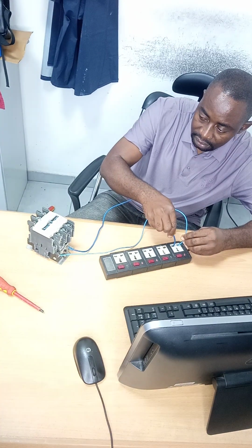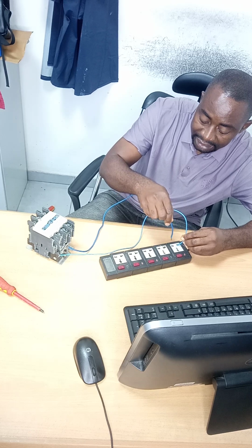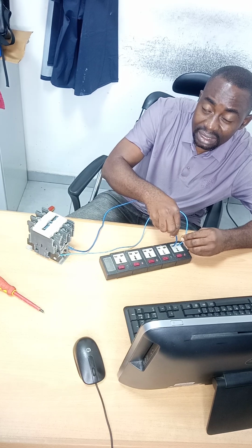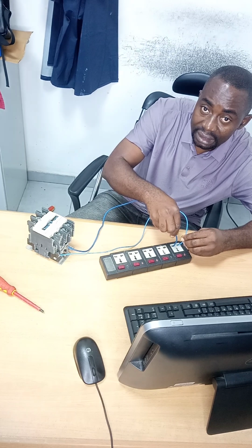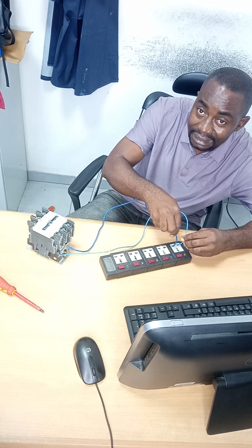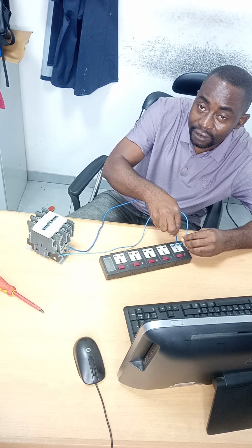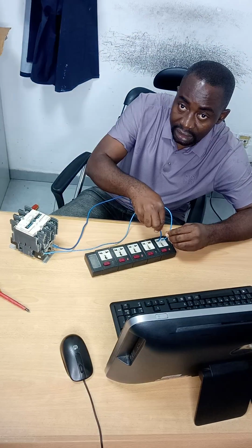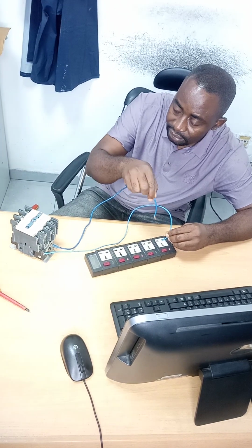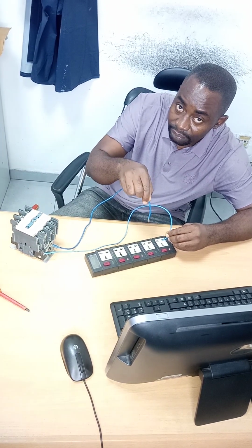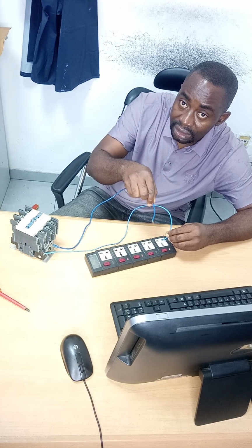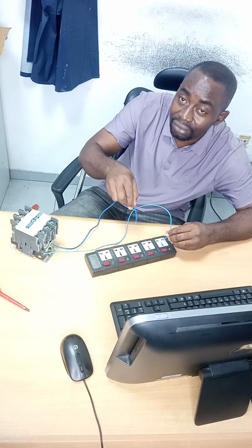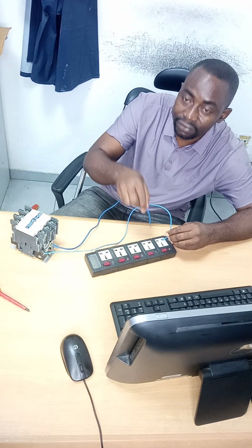Now, are you hearing that contact? Once you hear that contact, it's not expected to vibrate. After contacting, if you hear any form of noise, then that will tell you that the contactor is not functional. And if you also test and that contact is not proper, then the contactor is bad. So you can replace it right from there and test the one that they are going to give you again before you leave that point.